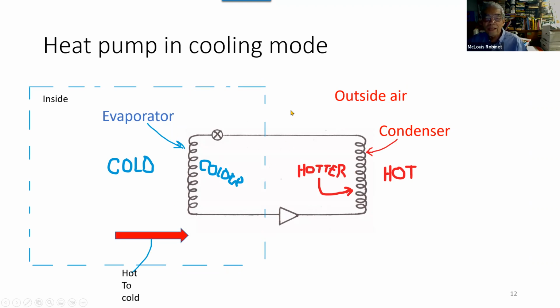Another reality of a real system is you'd have a thermostat. The thermostat would tell the compressor to turn on. So it would turn on, run full speed, and then the thermostat says turn off, and the compressor turns off. And so you go up and down, up and down. A better, more efficient system would be if this compressor could just respond to the load and not overshoot it.